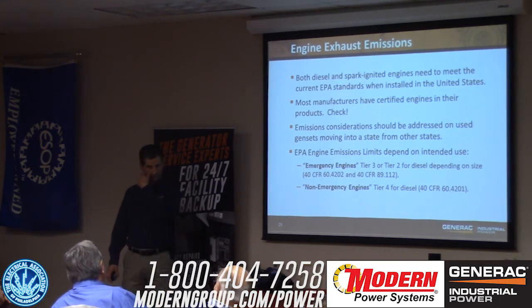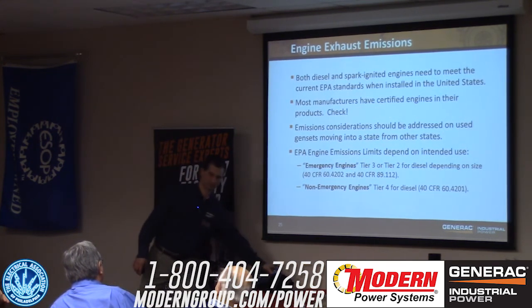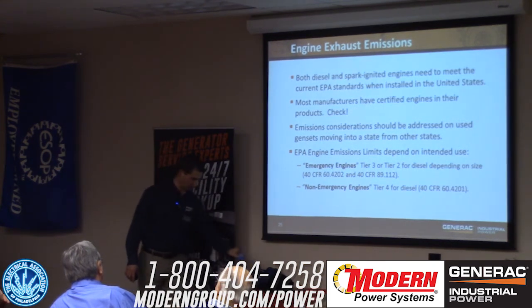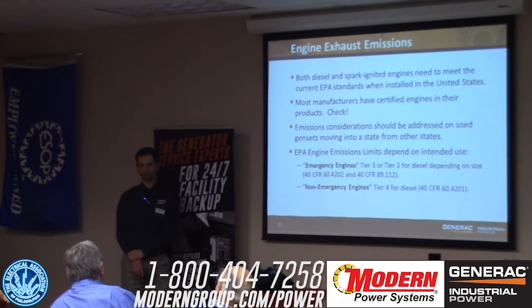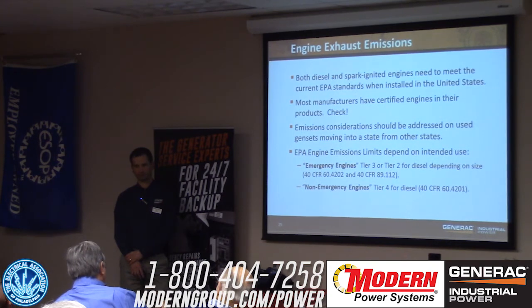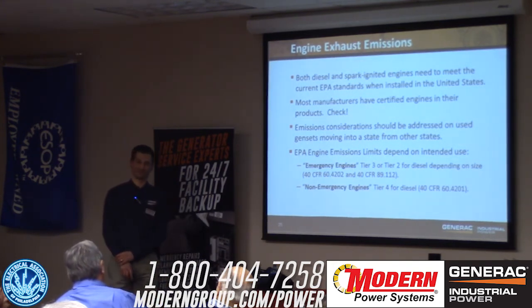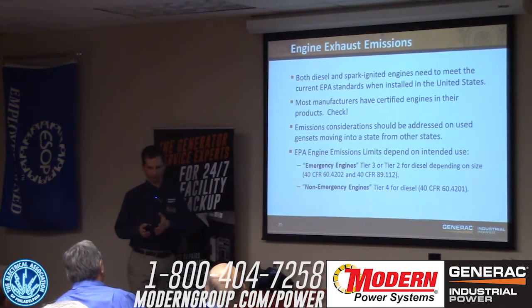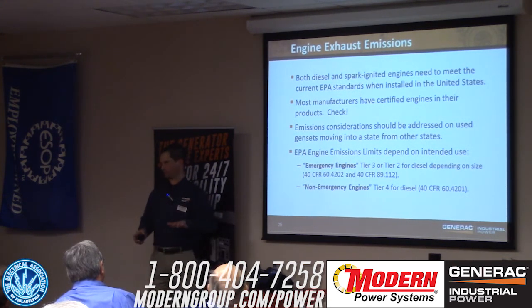We had some large 2 megawatt units installed, and the facility was limited to the number of hours they were allowed to operate per year, because they were only allowed to contribute so much to the atmosphere. When they did the commissioning, they found out they were actually putting out more, so they had to pull their hours back. That's when you get into a Title V air permit, where you start tallying up the hours and how much each contributor puts in. Most of you here are never going to run into that, you'll fall well below a Title V threshold. They had eight 2 megawatt units, plus a few other things on their campus putting stuff into the air.